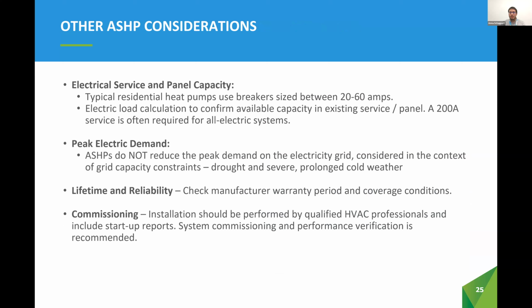Other air source heat pump considerations include the electrical service and panel capacity. Typical residential heat pumps use breakers sized between 20 and 60 amps. Now, an electric load calculation should be performed to confirm the available capacity of the existing service. And as a note, a 200 amp service is typical for all-electric air source heat pump applications.